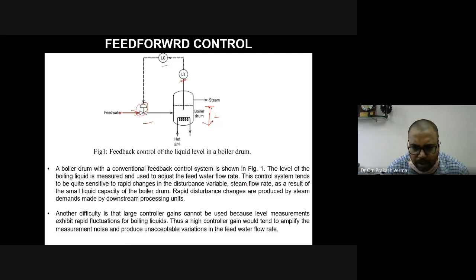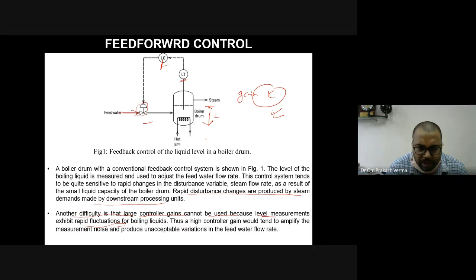So what is the problem in this? Rapid disturbance changes are produced by the steam demands. Another difficulty is that larger control gains cannot be used. Whatever the gain of this controller, K, the value of K should not be very high. Why? Because level measurement exhibits rapid fluctuation. If the gain is very high, then whatever fluctuation comes will be amplified in the level control, so that will not work. This is the problem.